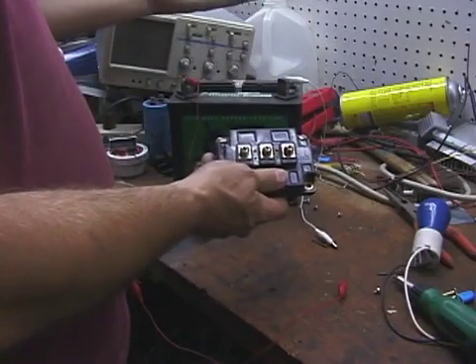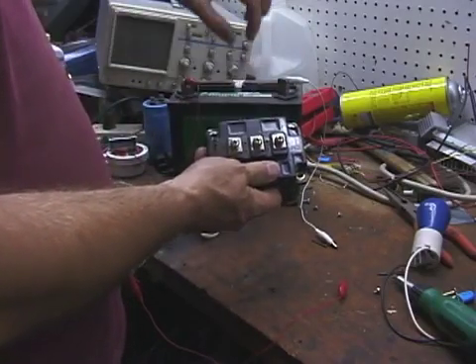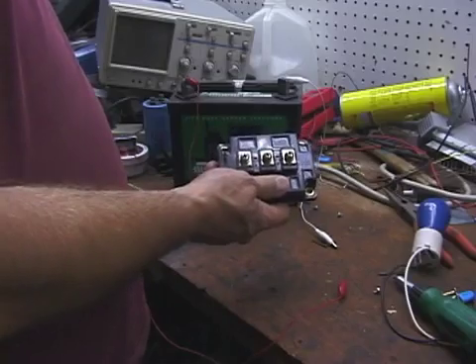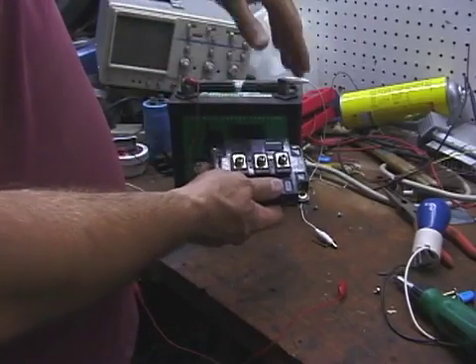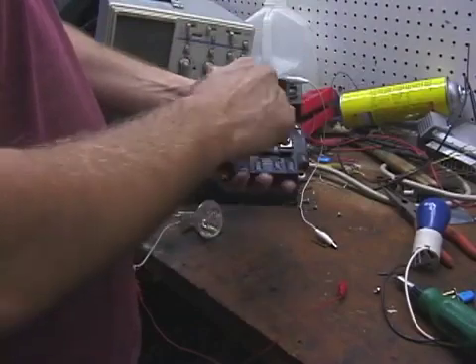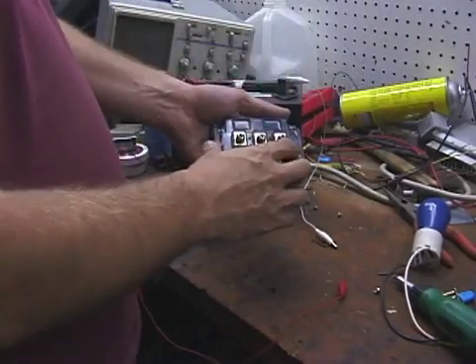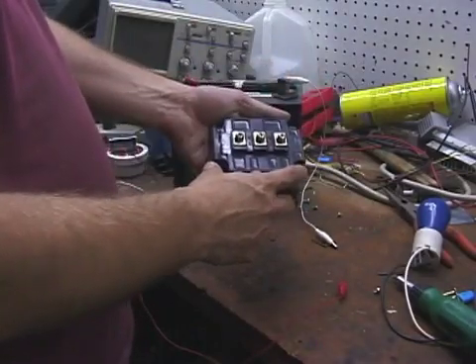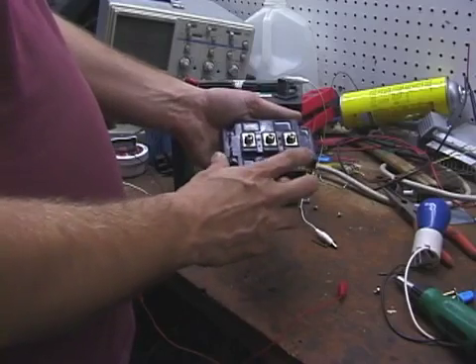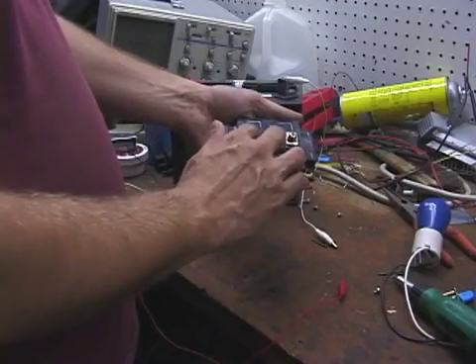There's usually three of these next to each other, cascaded on a DC power bus, and then each one of these goes off to a motor. Probably goes through a series of filters to get a better waveform, cut down on harmonics. But anyways, this is actually designed to drive an H-bridge.